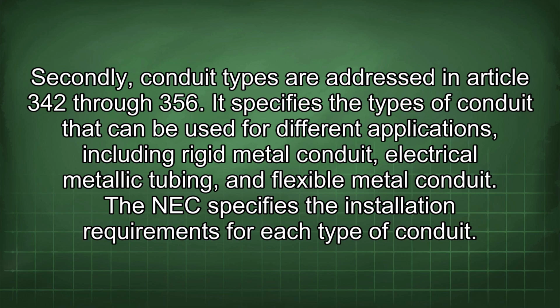Secondly, conduit types are addressed in Article 342 through 356. It specifies the types of conduit that can be used for different applications, including rigid metal conduit, electrical metallic tubing, and flexible metal conduit. The NEC specifies the installation requirements for each type of conduit.